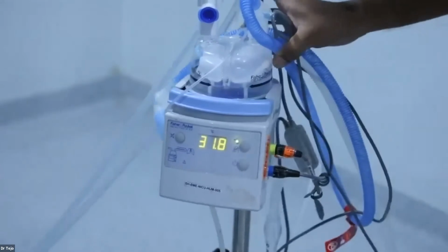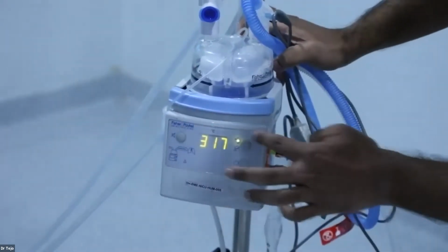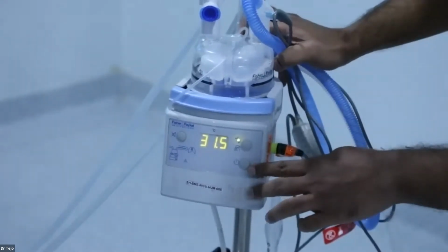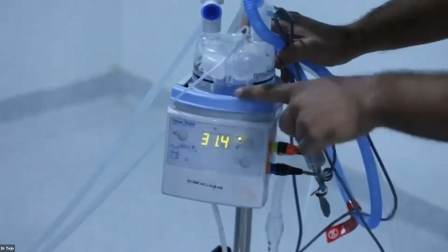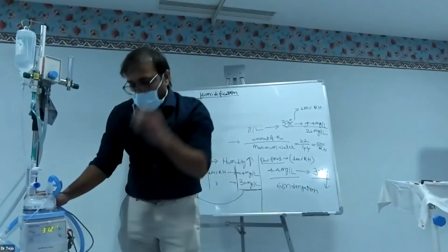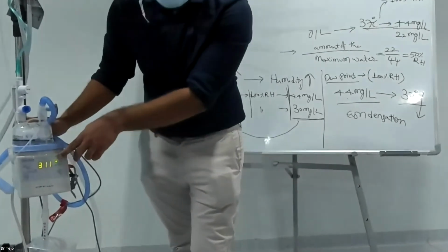Before coming to the alarms, I will show the buttons on the humidifier. This is the MR850, having these three buttons mainly. This is the power on and off button, and this is the mode button of the CPAP humidifier. Here you have non-invasive mode for the humidification and invasive mode for the humidification. In the invasive mode, we always aim for 100% relative humidity with a temperature of 37 degrees centigrade.